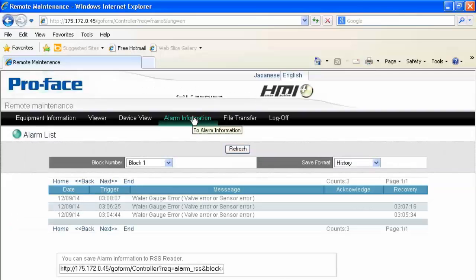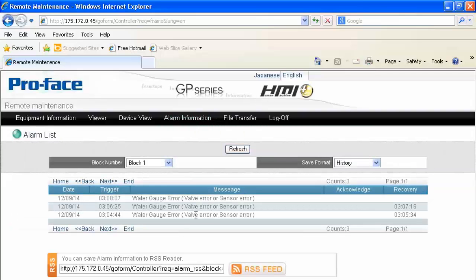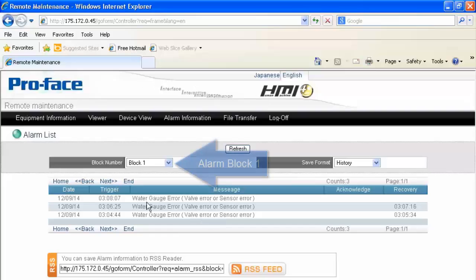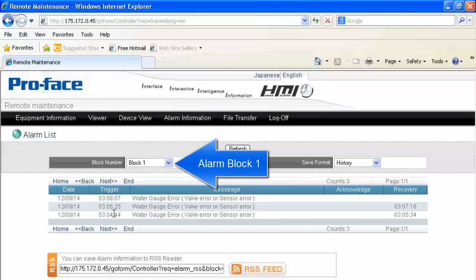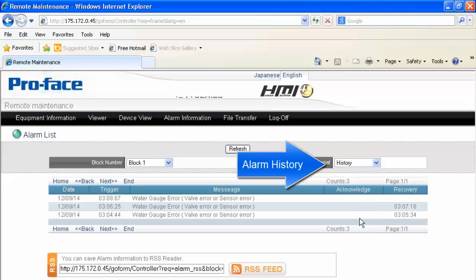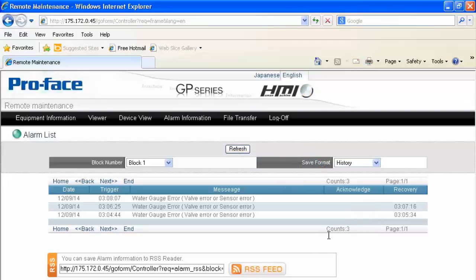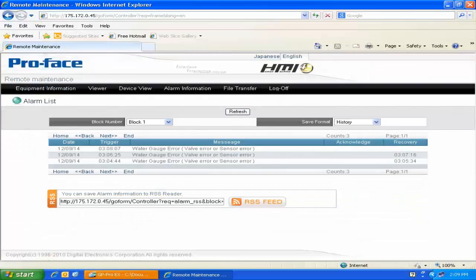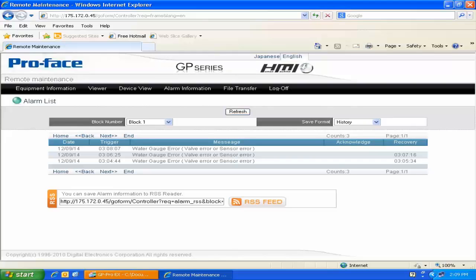Over in the Alarm Information tab, we can see there are already some alarms. In this particular case, there's a water gauge error that occurred at 3:04, 3:06, and 3:08 today. We can also see the recovery, and no one has acknowledged it because we just did a download to the HMI. There are other features available via this web interface, but we're not going to cover those in this video. For more information, please refer to the GP Pro EX manuals, available for download online or within the GP Pro EX software. Thank you.